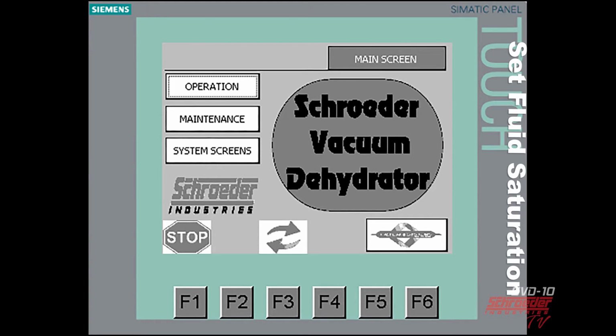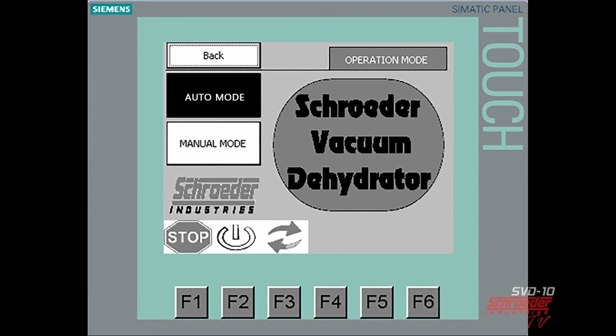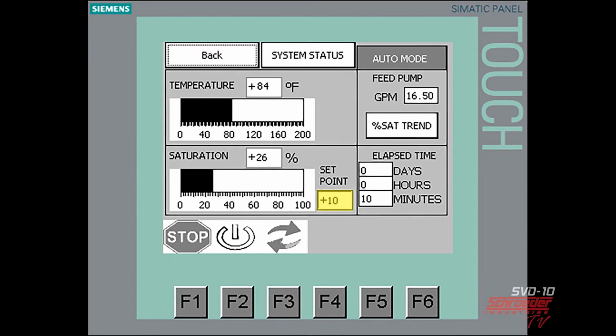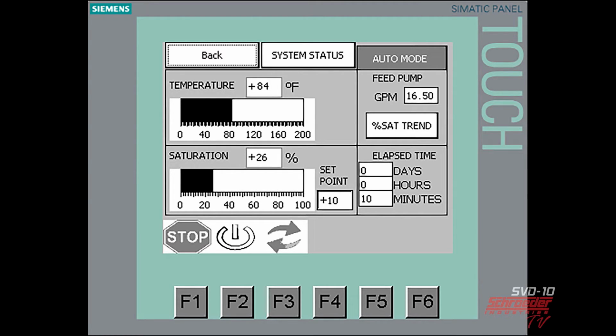To set the fluid saturation, click on Operation on the main screen, then click on Auto Mode on the Operation Function screen. Then select Set Point in the Saturation section on the SVD Automatic Mode screen and type in the desired saturation level. The current percent saturation can then be observed on the scale. To set the temperature, select the Set Point in the Temperature section and then type the desired temperature. Note, the temperature set point is only available on units equipped with a heater. All values during testing can be reset by selecting the appropriate set point again.